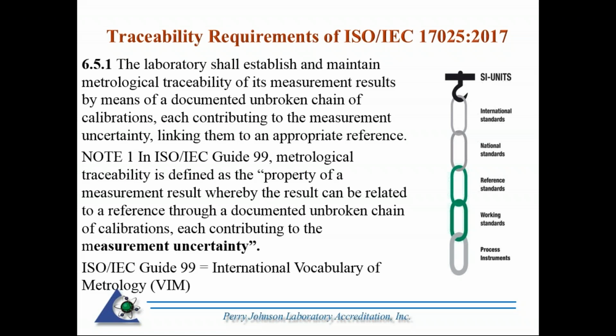maybe at a higher echelon calibration lab, or maybe directly at the NMI, the National Metrology Institute. They would have an uncertainty associated with that, which would be a component of their uncertainty, correlated to the uncertainty provided to the lab. So ideally, if this chain had uncertainty included in it, each one of those links would be a little larger the further you get away from the international units of measurement, in the U.S. if it's going through NIST, for example, starting at NIST.